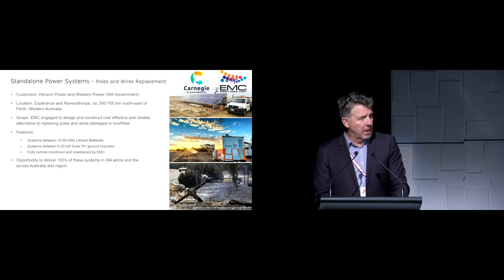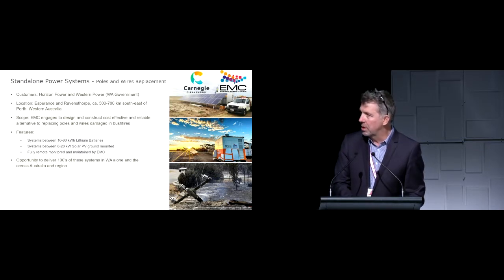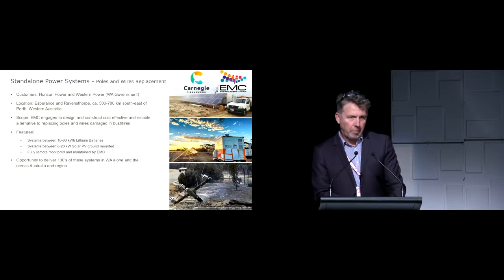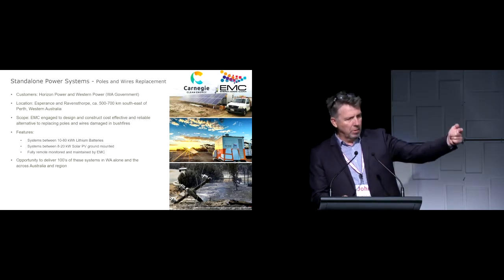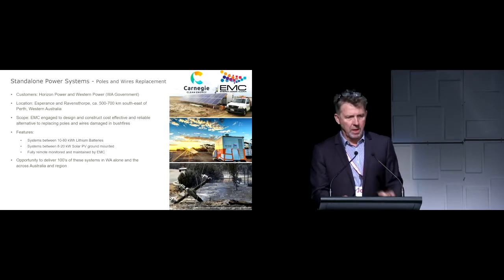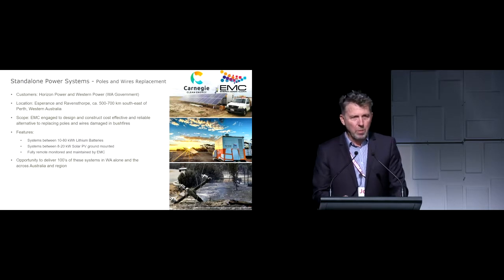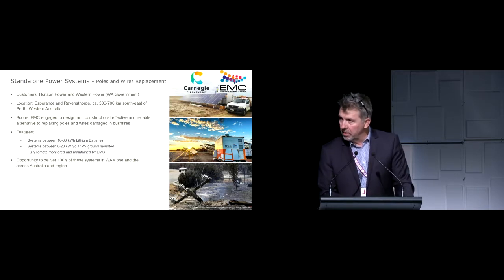Down in our southwest, in our wheat fields, a year and a half ago we had massive bushfires and tragically lost life and property. The power utility, Horizon Power, lost a lot of poles and wires, and found very quickly it was more economical to install a mini microgrid, a standalone power system, instead of replacing them. The economics are such that if there's more than 4 poles, it's cheaper to put in a standalone power system today, and that threshold will come down. We're talking about poles and wires that run as far as the eye can see, so there are hundreds of sites where ageing poles and wires can effectively be replaced.